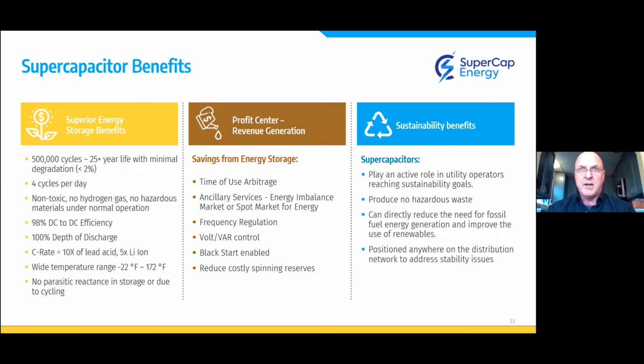Many solar systems can't operate without storage. A residential solar system typically can't operate without frequency and voltage signals sent by the utility, so when the power goes out, your solar system goes down with it. This type of system would bring those back up and keep them operating, and smarter inverters are capable of running off grid. That allows them to reduce the spinning reserve as you level out the power curve through the day, so less fossil fuel fired spinning reserve, particularly for natural gas generation, is needed.